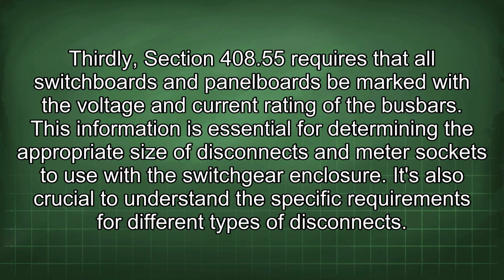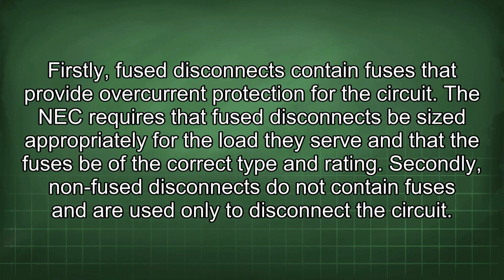Thirdly, Section 408.55 requires that all switchboards and panel boards be marked with the voltage and current rating of the busbars. This information is essential for determining the appropriate size of disconnects and meter sockets to use with the switchgear enclosure. It's also crucial to understand the specific requirements for different types of disconnects. Firstly, fused disconnects contain fuses that provide overcurrent protection for the circuit. The NEC requires that fused disconnects be sized appropriately for the load they serve and that the fuses be of the correct type and rating.